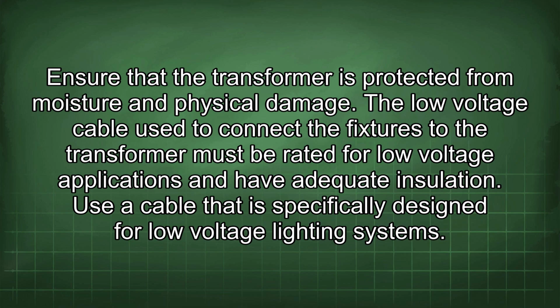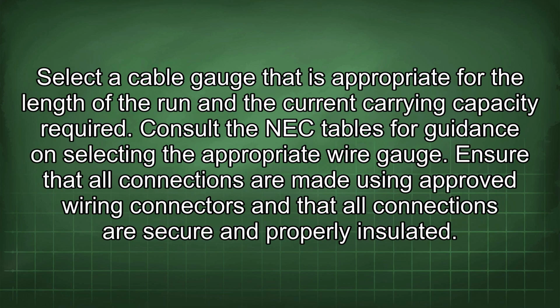The low-voltage cable used to connect the fixtures to the transformer must be rated for low-voltage applications and have adequate insulation. Use a cable that is specifically designed for low-voltage lighting systems. Select a cable gauge that is appropriate for the length of the run and the current carrying capacity required. Consult the NEC tables for guidance on selecting the appropriate wire gauge.